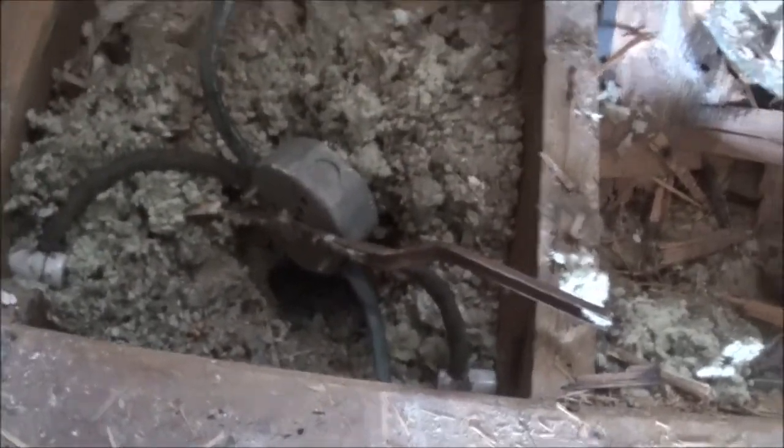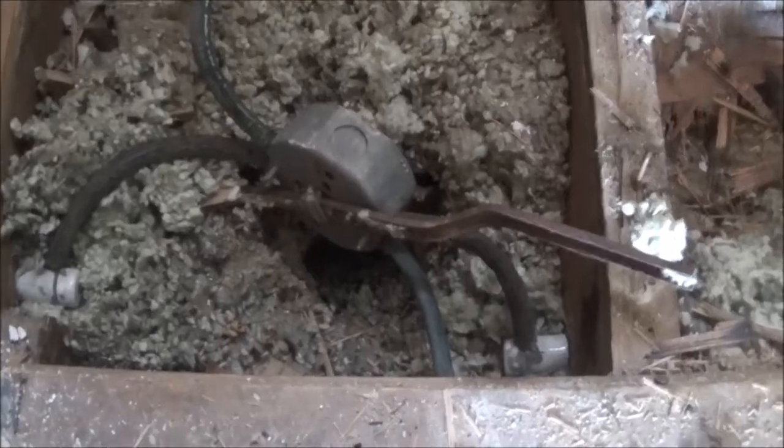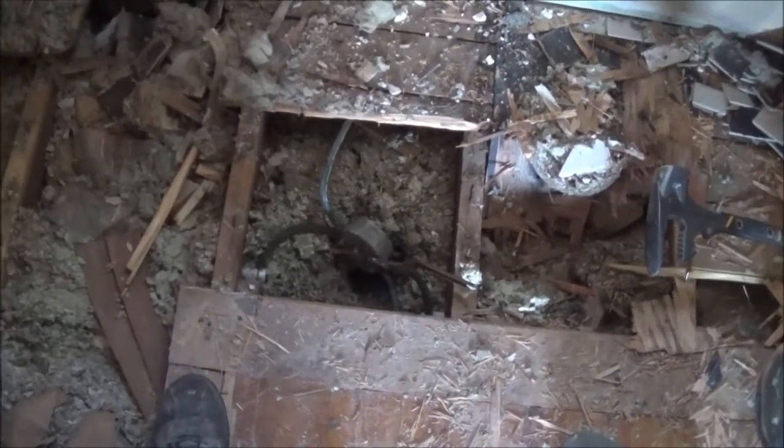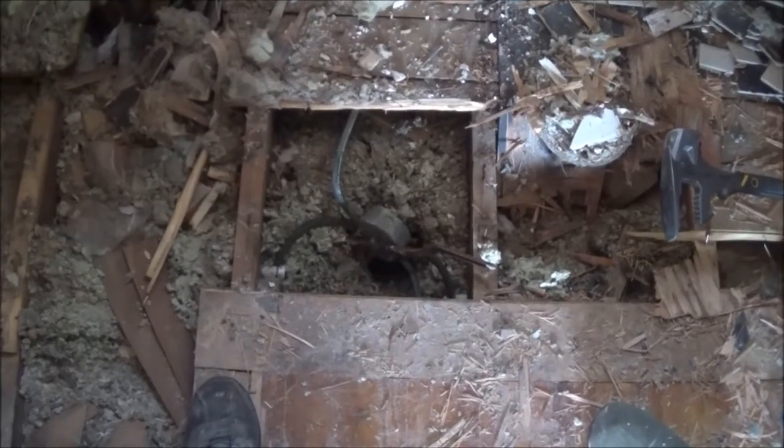The things you find in an old house. Tore up the floor and there just happens to be knob and tube — live. It's funny because this house has no fixtures running knob and tube. I've been in every apartment and changed all the 70s fixtures. There's no knob and tube anywhere unless it's simply being used as a junction point. So I'm going to go into the whole main floor and second floor, have all the fixtures tested, disconnect the legs of the knob and tube, recheck everything, and make sure it's all dead. If it is, I'll just leave it disconnected — it's a little concerning knowing that it just vanishes this way and is probably not connected to anything. There's a hidden junction point in the floor.